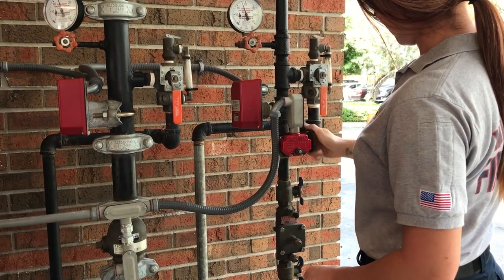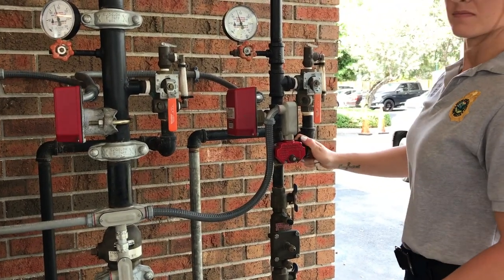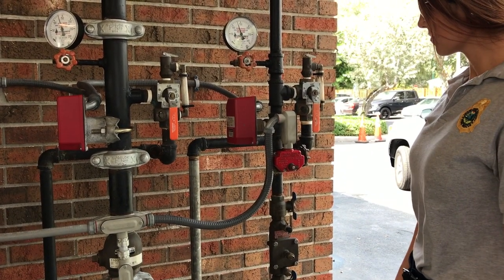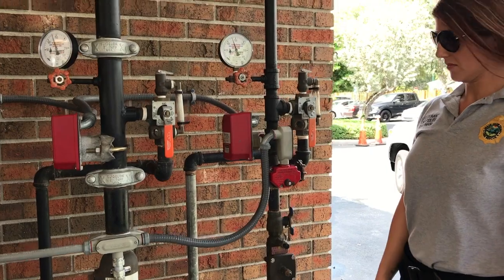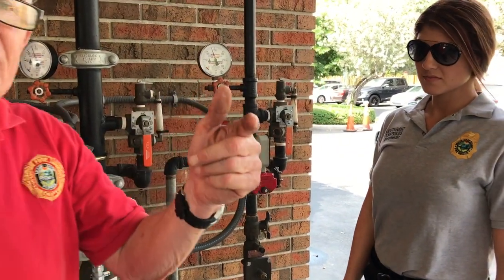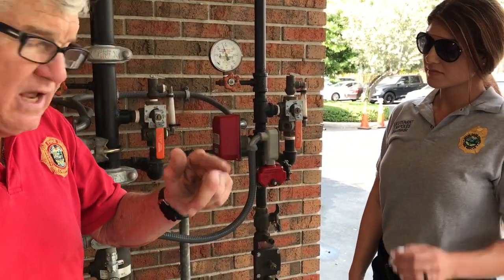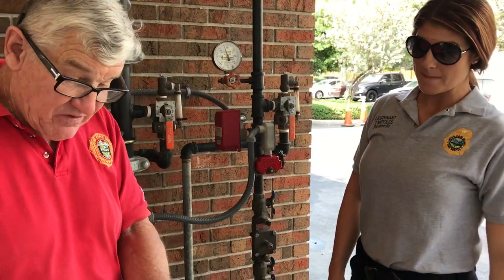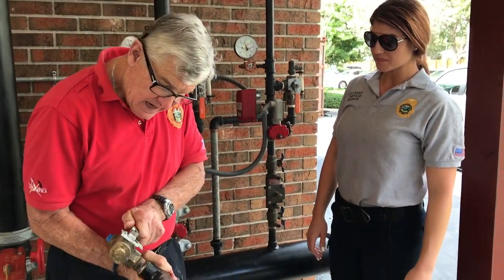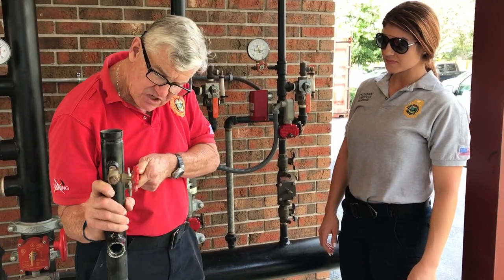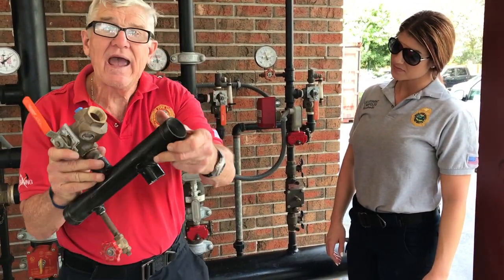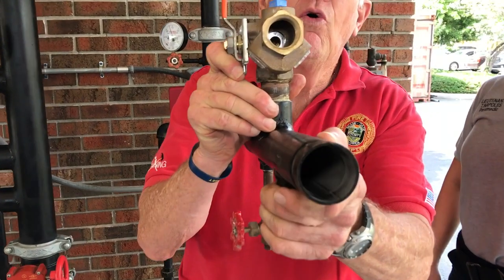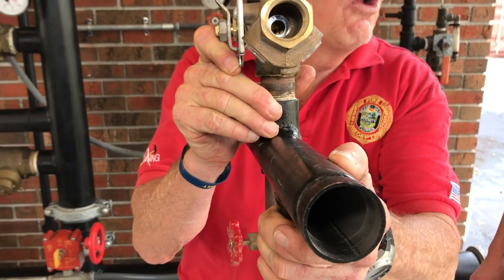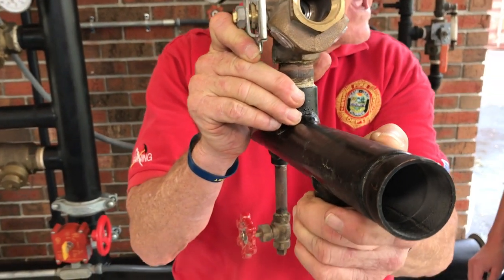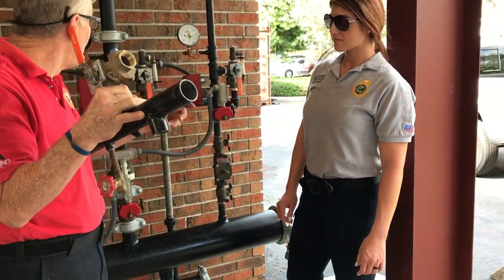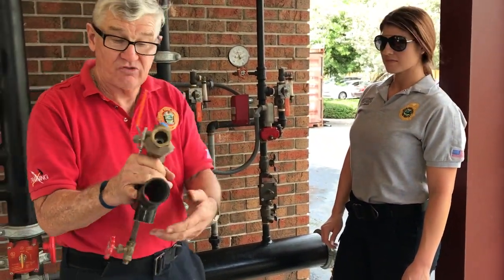Okay, and then just stand by there for a second. Now, she's going to operate this valve. This valve has three positions: off, test, and drain. In the off position, obviously, it's off. In the test position, it presents a half inch orifice that replicates the flow of one sprinkler head to test the function of our water flow device.